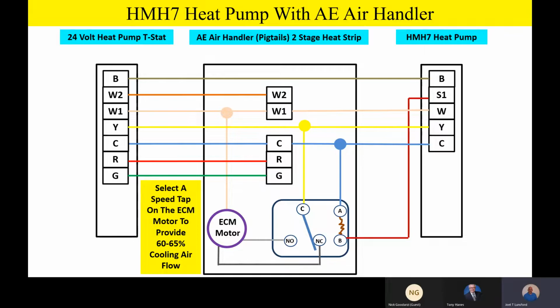So the point I'm making is that you want to get close to about 60 to 65%. Let's say, as an example, and I'm just making this up, speed tap number 3 gave me 675 CFM and we're looking for 720, and speed tap number 4 gave me 840 CFM. Which one would I pick? Well, I'd pick the one that's closest to 720, which in this example would be speed tap number 3. So we always want to make sure our contractors and customers understand that when they set these up, they're going to have to measure the airflow. We want 100% airflow on the normally closed contact of the relay, and we want to select a speed tap on the normally open contact of the relay for about 60% airflow.